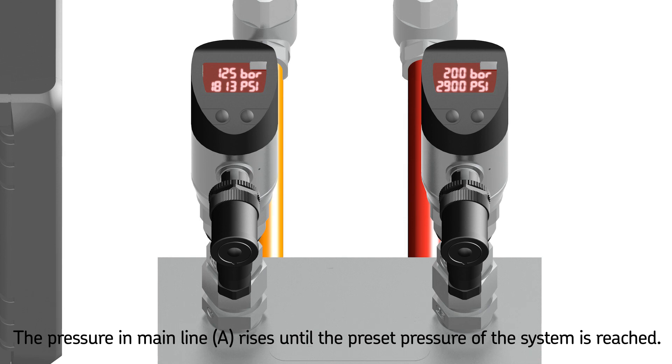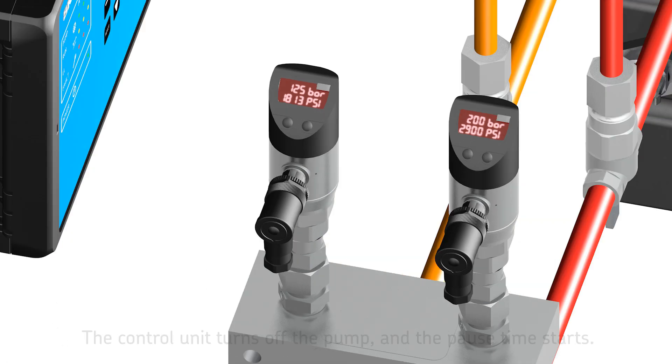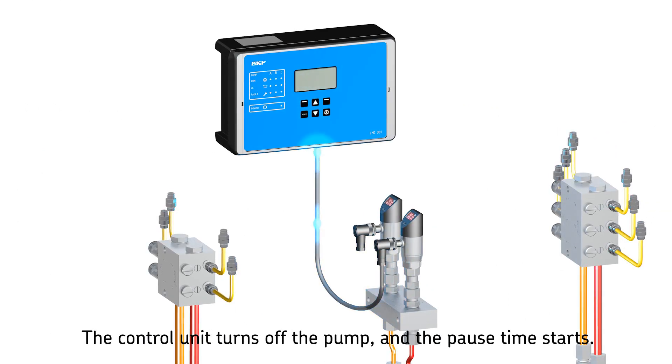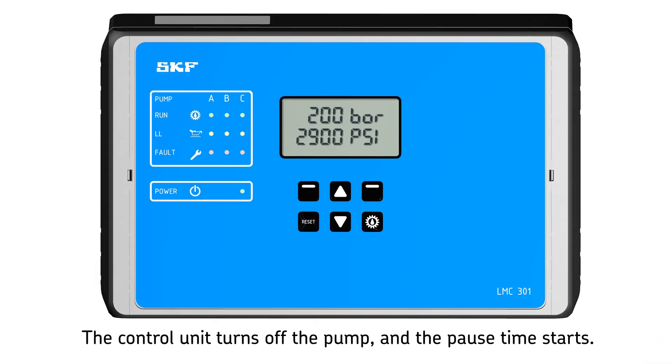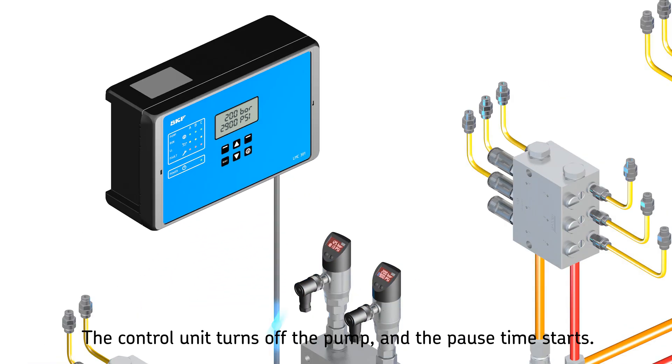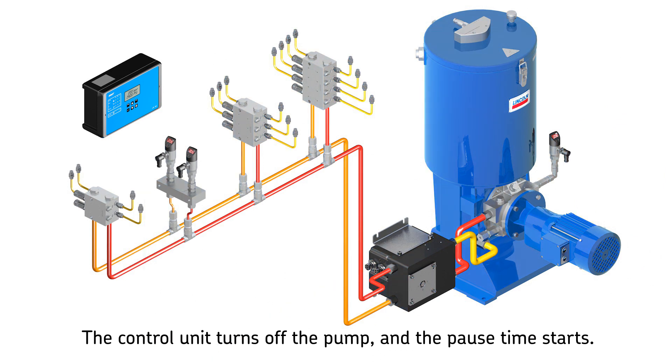Pressure rises until reaching the preset level at the end-of-line pressure switch, mounted in the main line prior to the last metering device. The pressure switch signals an electric pulse to the control unit, which turns the pump off and signals the changeover valve to relieve main lines A and B, starting the pause time.